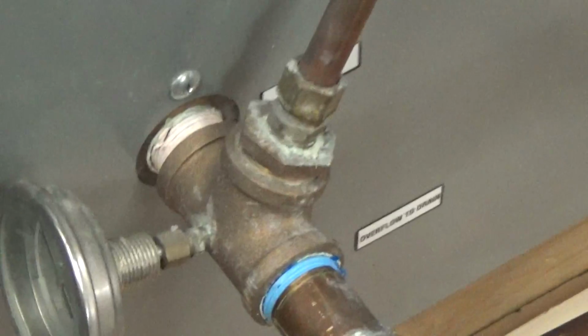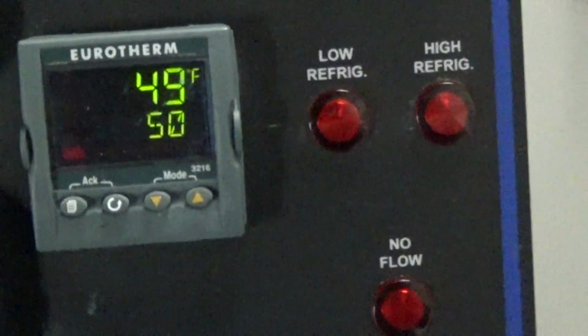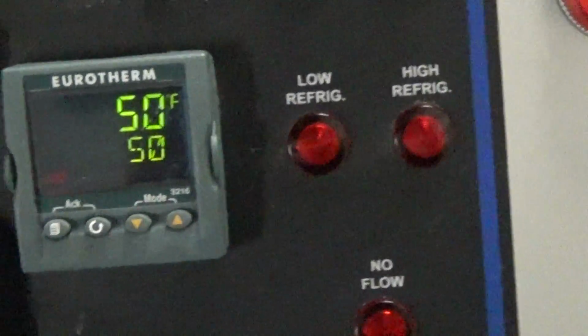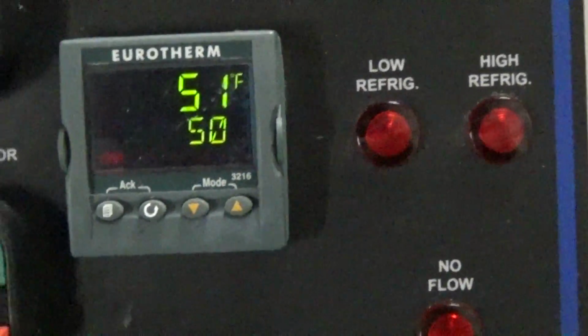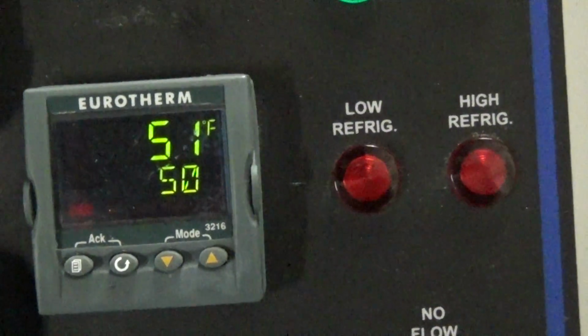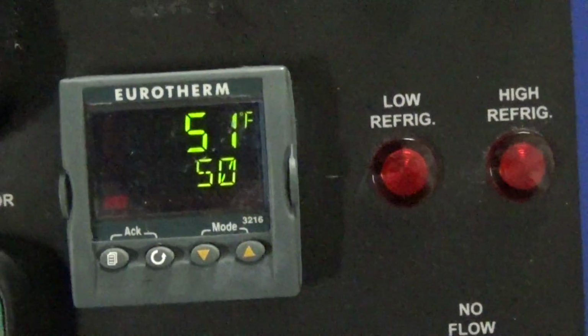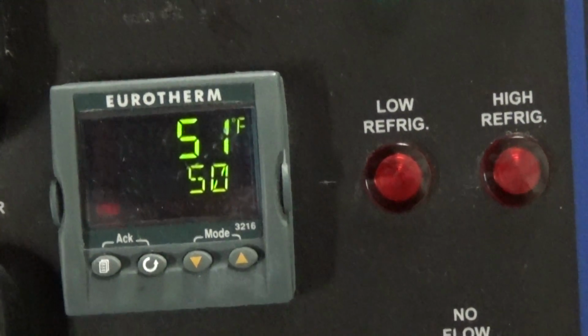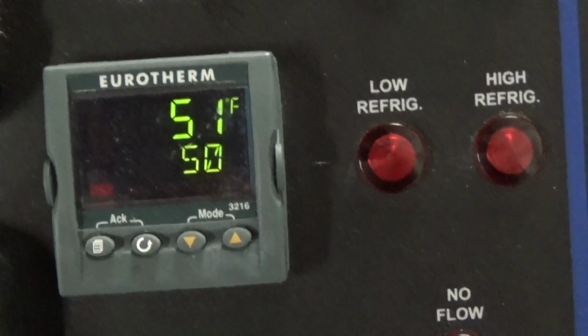This is going to ship out with the factory installed bypass, which is this line right here from the inlet and outlet. And it also has some redundant pressure gauges here on your inlet and outlet also, which is kind of nice. And this is your bypass to adjust it. You can hear that little hissing noise. It's the hot gas bypass. So this goes approximately, set point 50, this goes approximately 3 degrees below, and then I'll let it go back up, and then start chilling again to maintain your set point temperature.